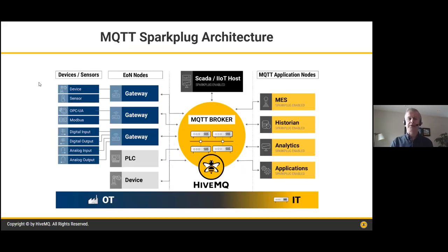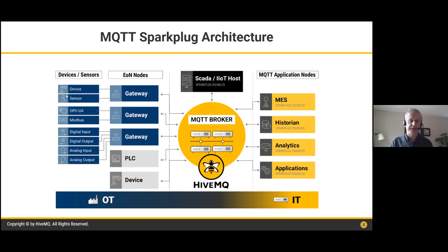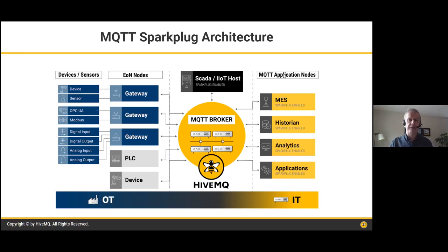A Sparkplug architecture has edge-of-network nodes on the left — gateways, or modern PLCs that can speak Sparkplug natively. Gateways can take data from legacy equipment speaking OPC-UA, Modbus, or various digital and analog I/O. Edge nodes communicate through a broker — in this case HiveMQ — to application nodes: different types of applications that connect to data through the broker, with a SCADA system doing overall coordination.